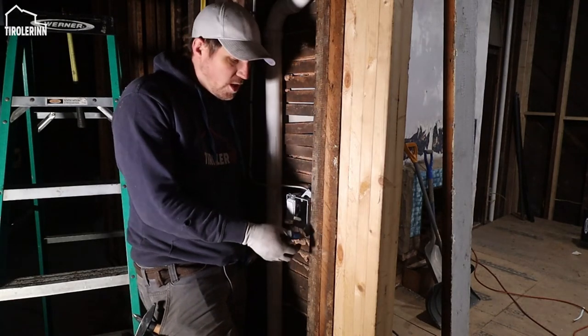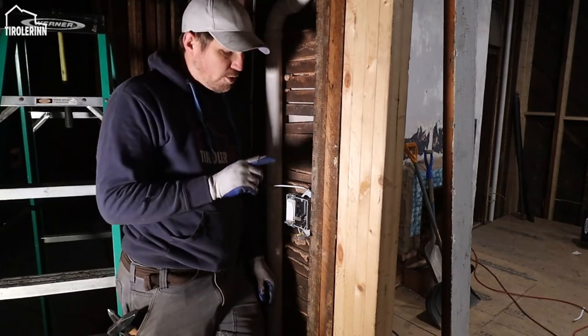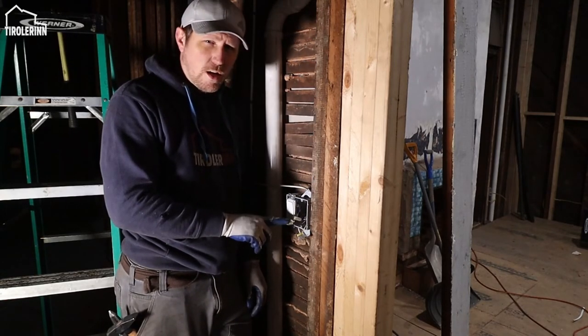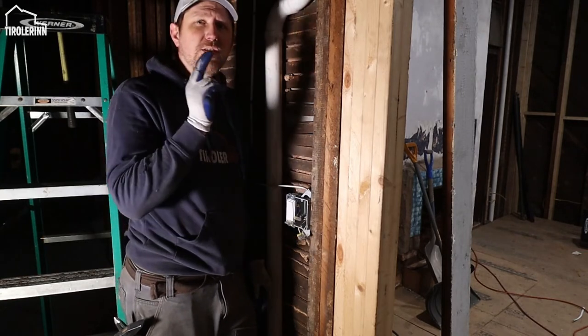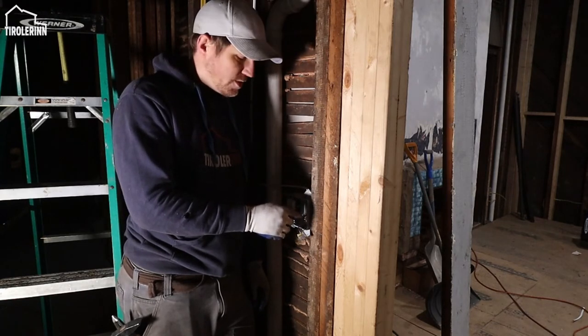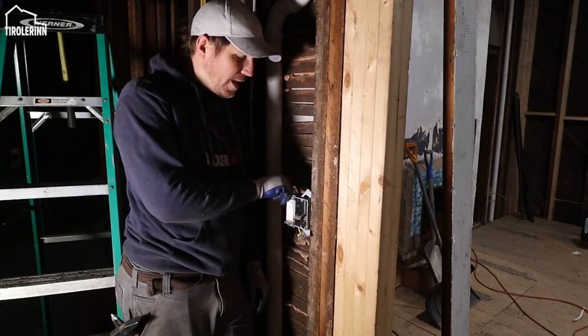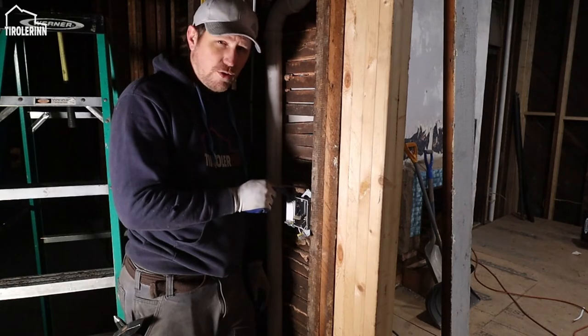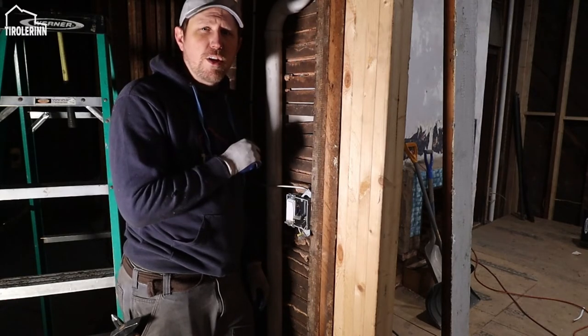If you're wondering why I use these connector pieces in the boxes, and I actually have them hanging out, the main reason I'm using them is when I come into a double box for light switches, I need to have at least three hot and three neutral, meaning obviously the one that is coming in plus the ones that are going to the first circuit and then going to the second circuit. When I come to the ground, I actually need four, and for that is one coming in, of course, where it goes back to the breaker box, but then the other one needs to have one that can connect the entire box. So it grounds the box, the two light switches, and then each light itself needs to have a ground too. So I need to run that to each one of the lights too.